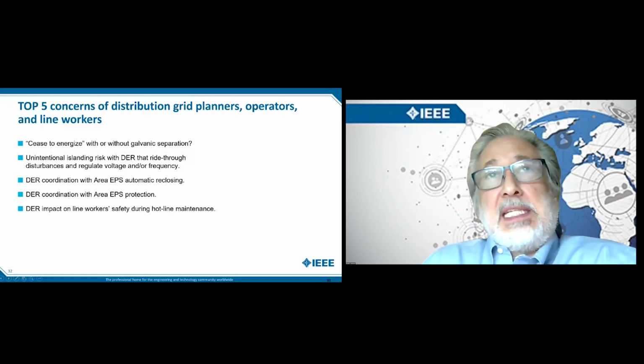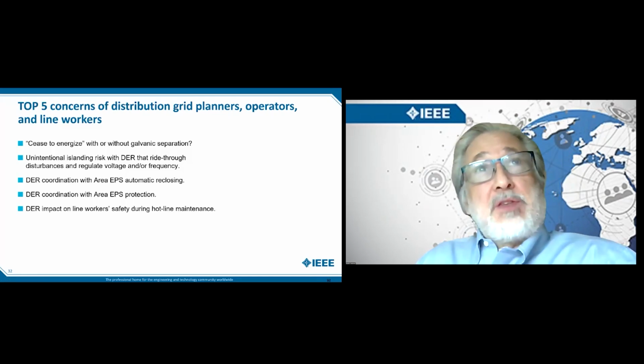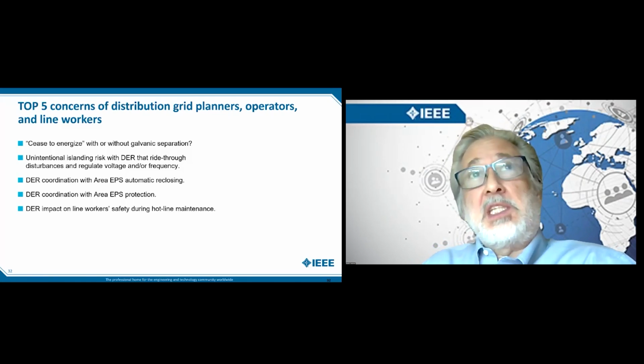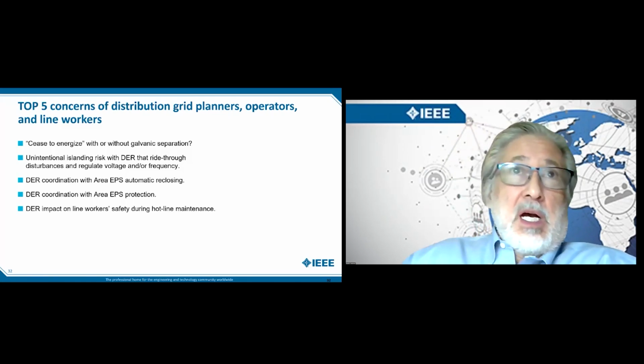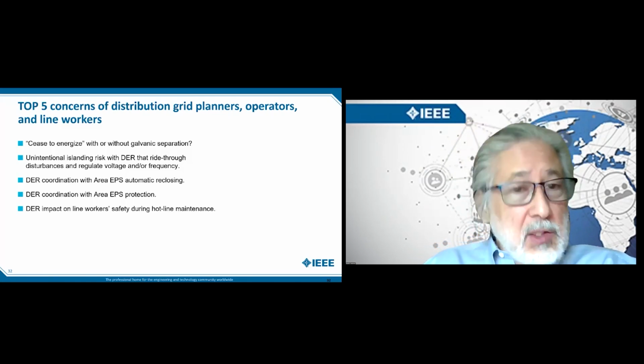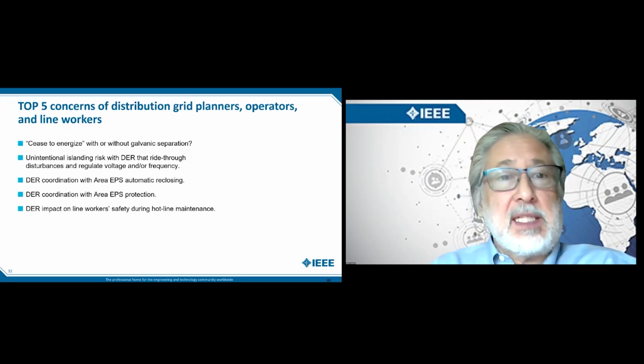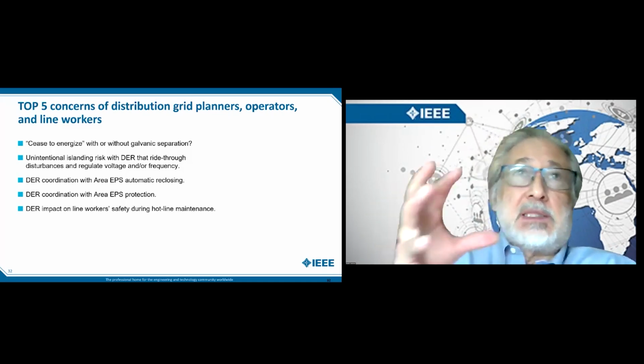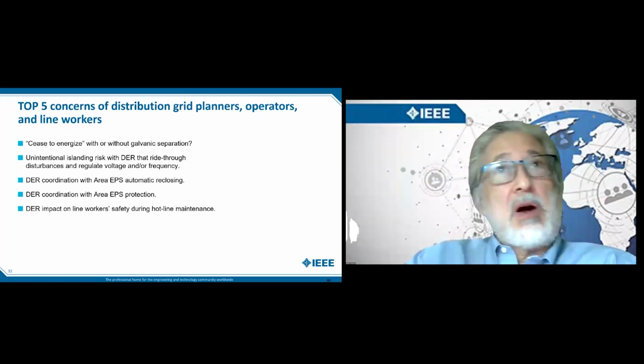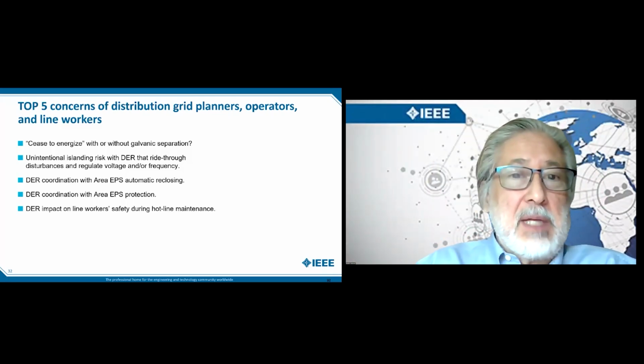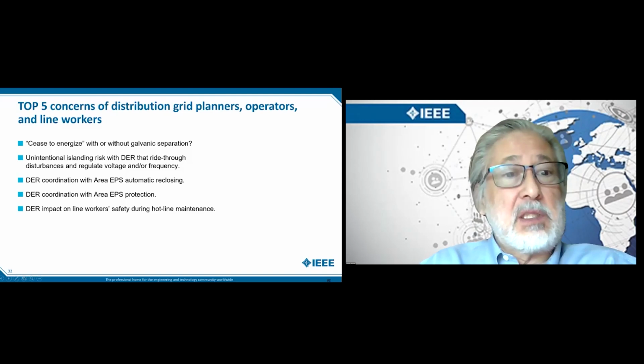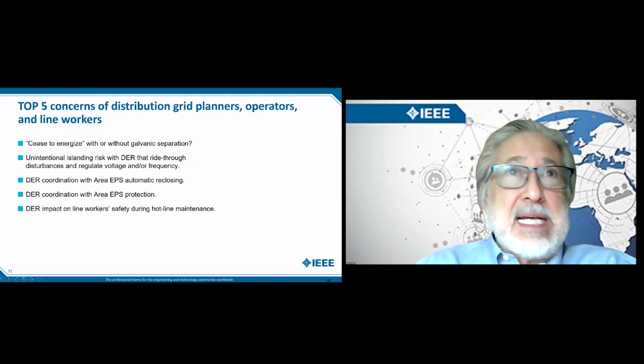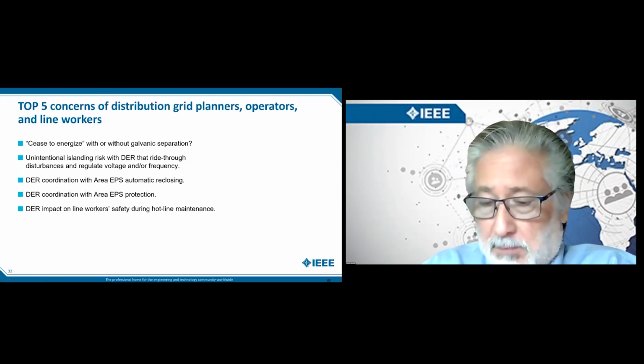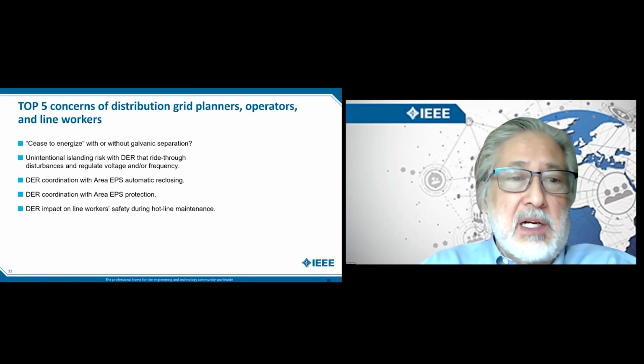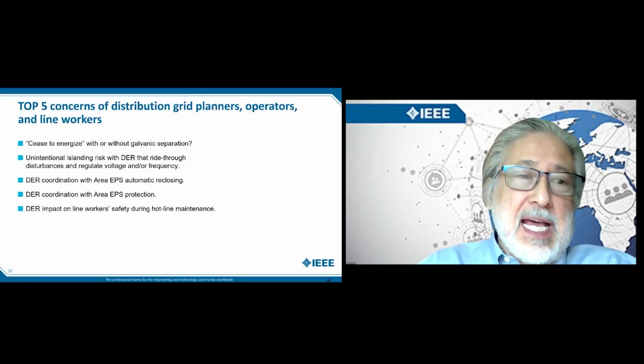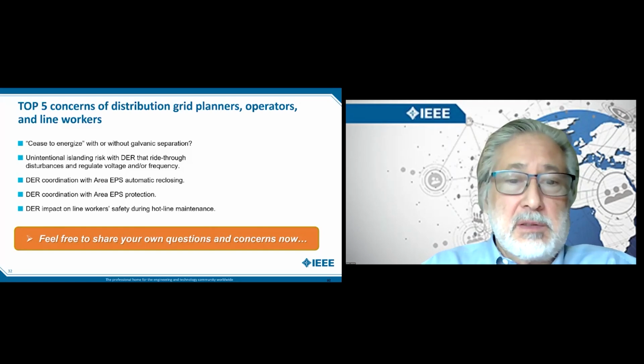A new stress is the need to have these assets ride through brief disturbances to continue supporting the grid versus tripping off. There's tension there, and it's an engineering challenge to balance the need to not backfeed a down grid but also not trip too quickly, continuing to support the grid through brief disturbances. As distribution systems get more automated, challenges arise in coordinating with DER. That last bullet ties back to the first two.